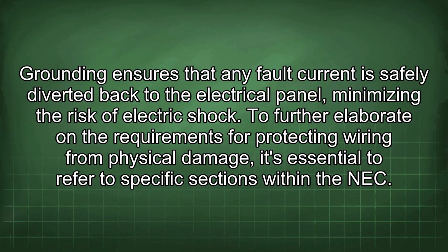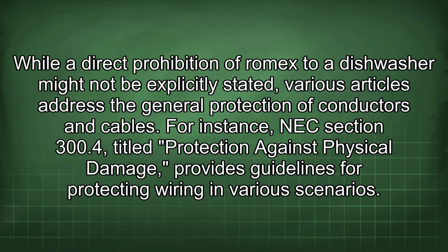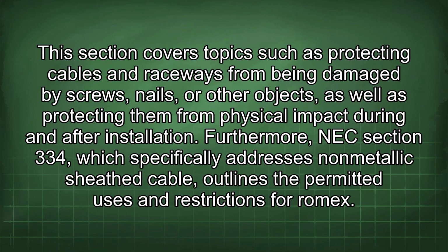To further elaborate on the requirements for protecting wiring from physical damage, it's essential to refer to specific sections within the NEC. While a direct prohibition of Romex to a dishwasher might not be explicitly stated, various articles address the general protection of conductors and cables. For instance, NEC Section 300.4, titled Protection Against Physical Damage, provides guidelines for protecting wiring in various scenarios. This section covers topics such as protecting cables and raceways from being damaged by screws, nails, or other objects, as well as protecting them from physical impact during and after installation.